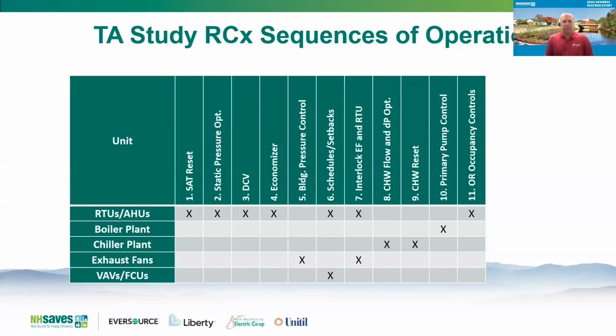Schedules and setbacks, one of the first things you always want to look at is just turn stuff off when you don't need to run it. Very, very cost effective. Interlocking exhaust fans and a rooftop unit, so that when the rooftop unit doesn't run, the exhaust fan will turn off. Really simple interlock measures can be really, really beneficial.